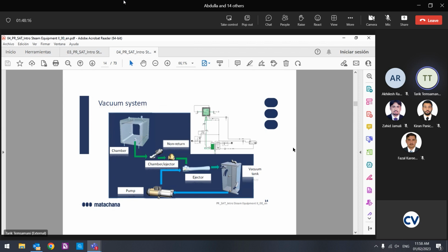Sometimes this pneumatic valve, this plunger valve, has a leakage. Yes, it is a pneumatic valve, it works with air. If there is low air pressure, the valve cannot open properly, and you can also get a problem in the gasket, because all of that works with air. The gasket is pressurized with air. If the air pressure is down, the first thing you get is the alarm for the gasket pressure. And of course the valve will not open properly.